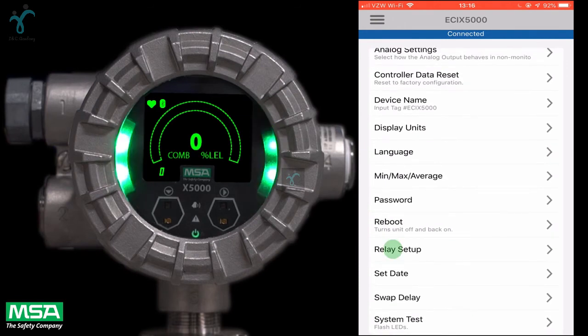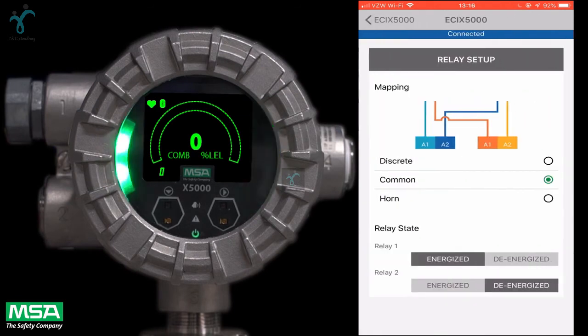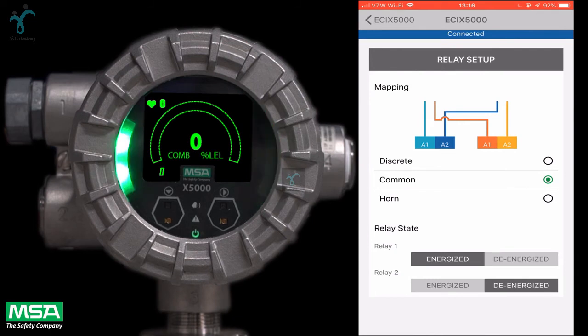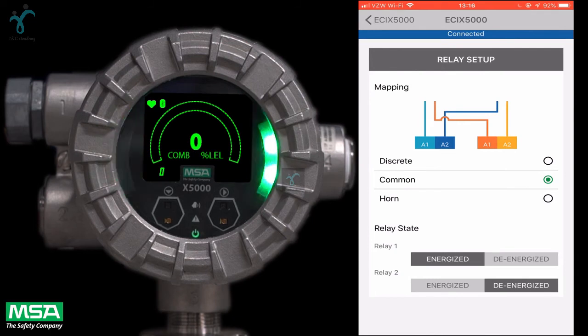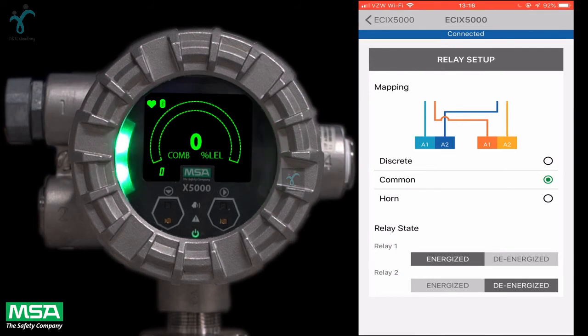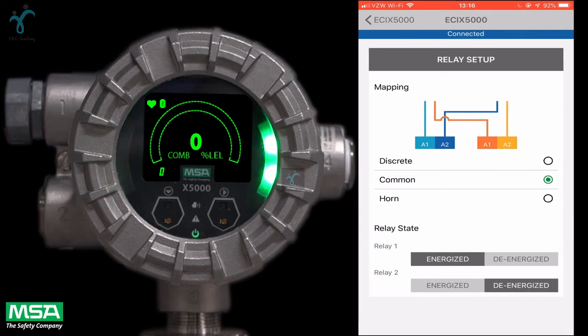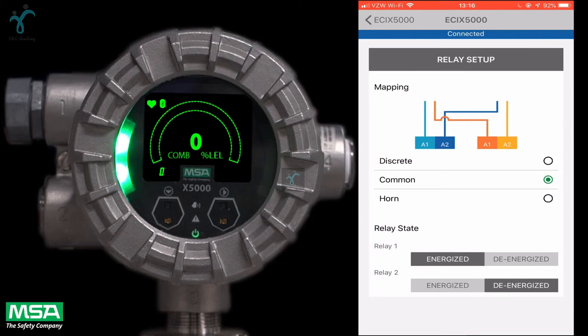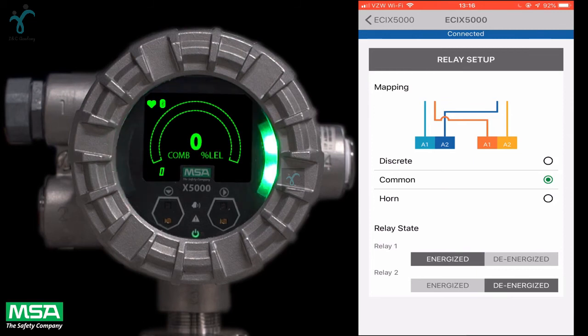Let's take a look at the relay setup next. Relay 1 and 2 can be set to common, discrete, and horn modes, and set to common as default. In common mode, relay 1 is actuated by alarm 1 and relay 2 is actuated by alarm 2.